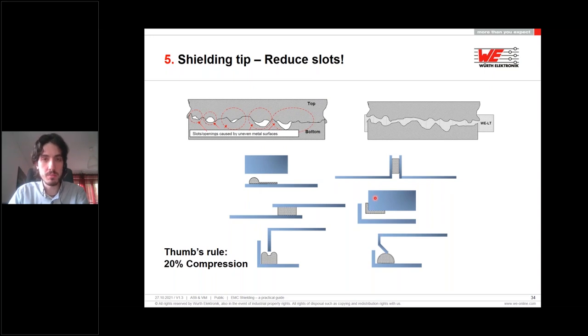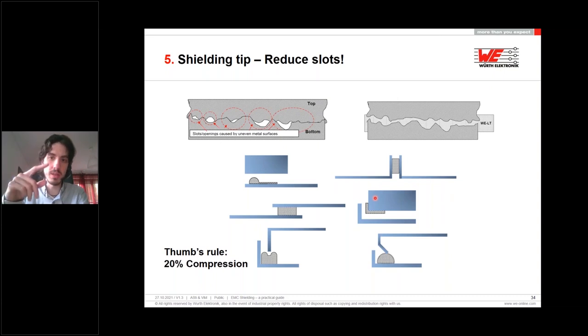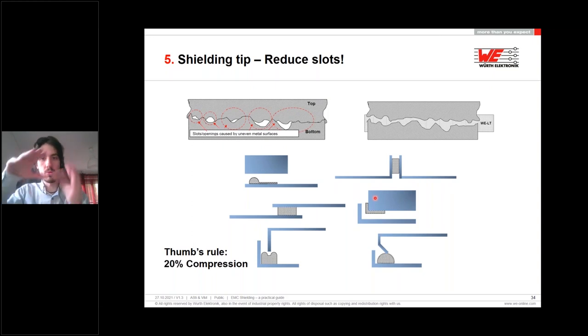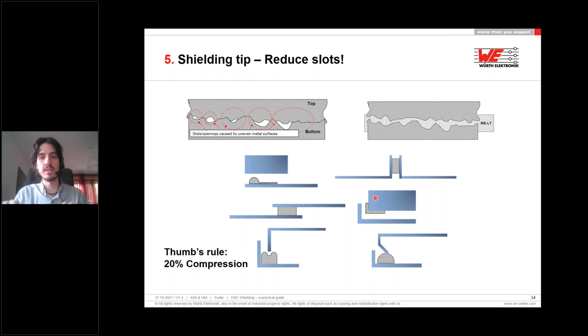An important rule about EMC gaskets: the gasket should always be compressed around 20% of its original height. This creates a full connection between the top and bottom layers — the gasket is gripped and compressed so that it makes a complete connection over the entire contact surface.